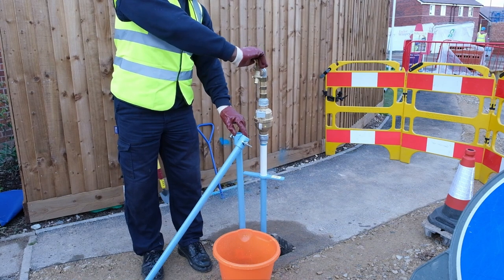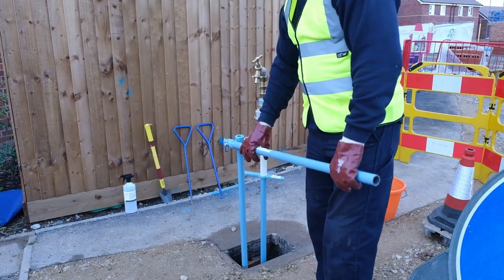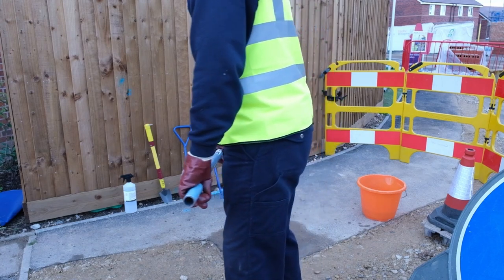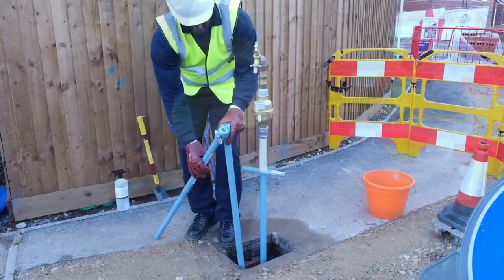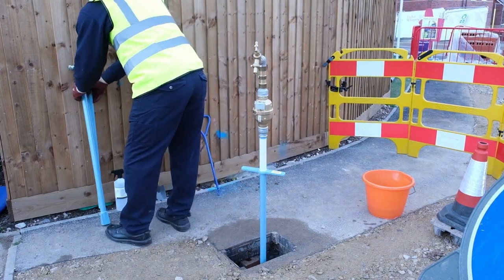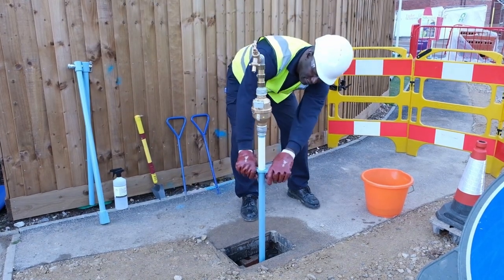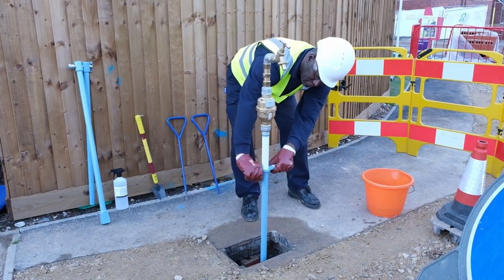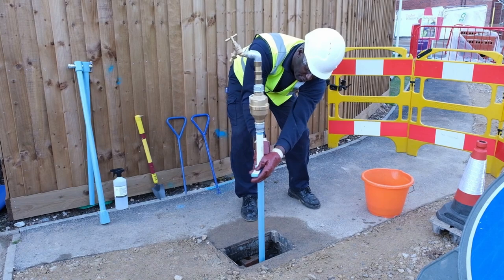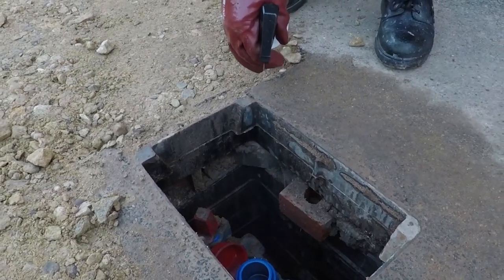Once you have collected the required amount of water, close the fitting. Reverse the process — close the hydrant in a slow and controlled manner. Finally, remove any attached equipment. Remove the standpipe via the handles. Remember, do not stand directly over the hydrant as a surge in pressure could cause serious injury. Disinfect the hydrant pit and standpipe.